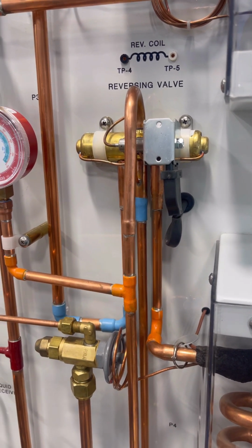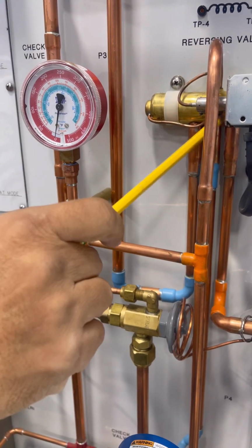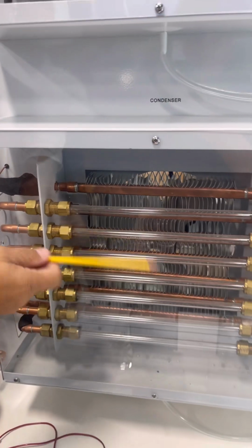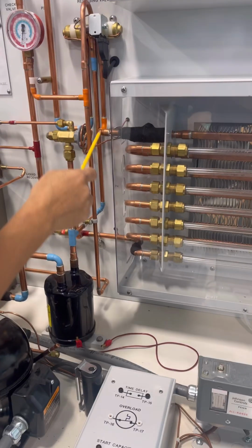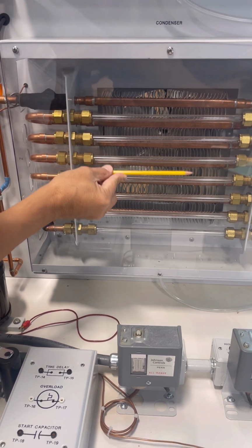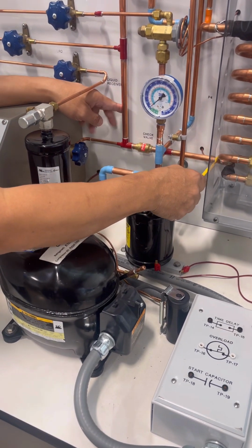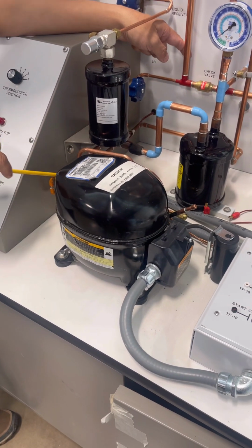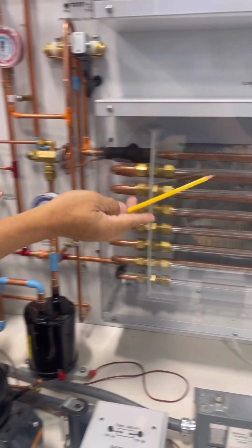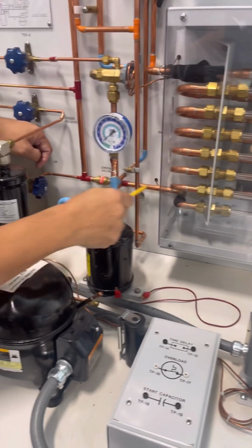If you choose AC or heating, it will switch to the left or switch to the right. So now let's choose AC. This one's going to move this way so that the freon comes out to this side. So now the freon goes to what we call the condenser. Vapor all the way to the middle, and then from the middle all the way down it turns to liquid. You understand? Let me repeat. The freon coming out from right here is vapor all the way, and from the middle going down, it turns to liquid. And the freon goes out here.